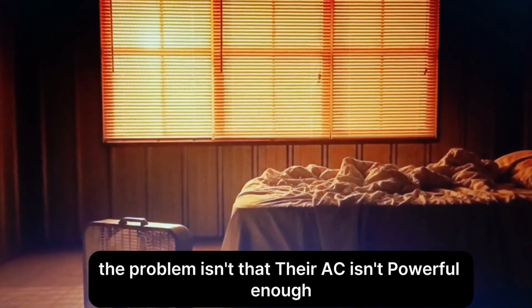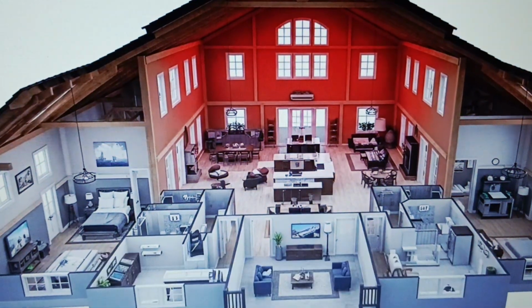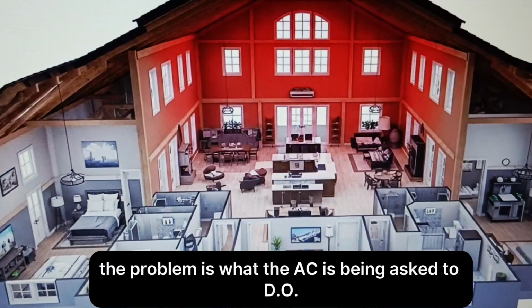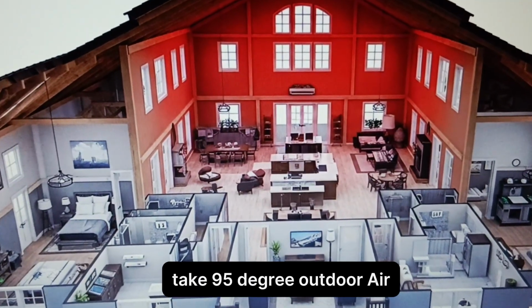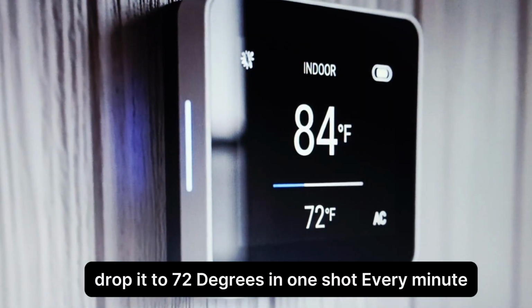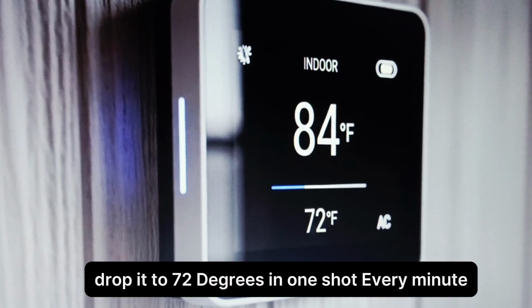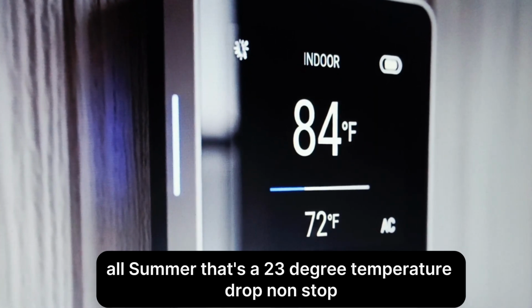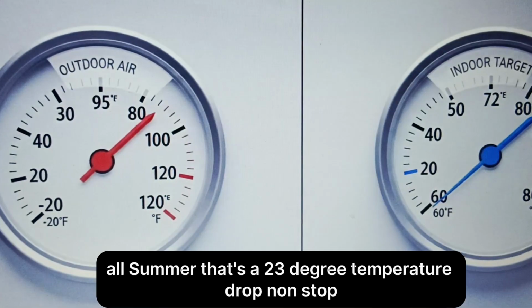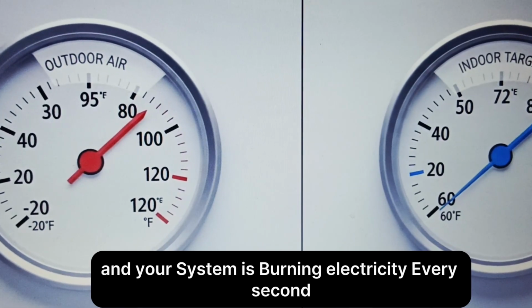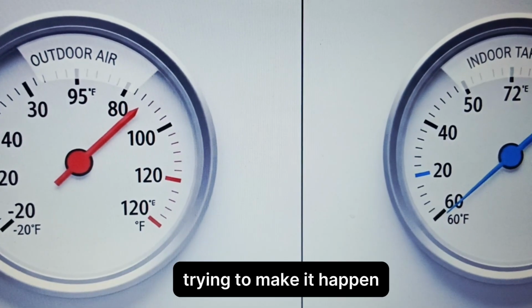The problem isn't that their AC isn't powerful enough. The problem is what the AC is being asked to do. Take 95-degree outdoor air. Drop it to 72 degrees. In one shot. Every minute. All summer. That's a 23-degree temperature drop, non-stop. And your system is burning electricity every second trying to make it happen.